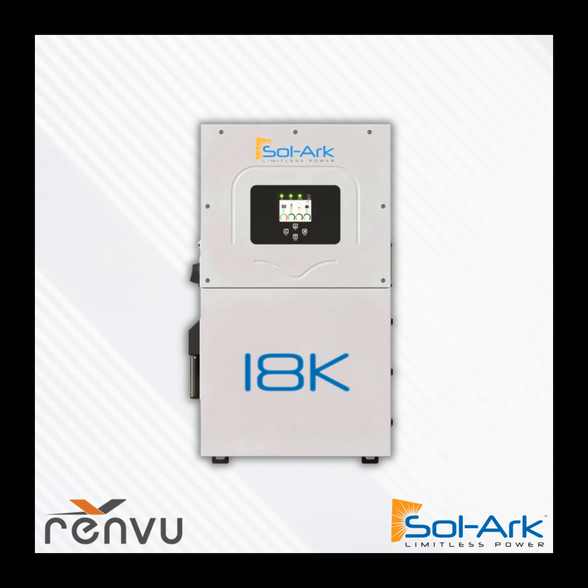If you are not going to power the rapid shutdown system off the manufacturer's AC power supply, and instead run your power off the COM board on the Sol-Ark, just know you can do it with the 18K far more than you could with the 15K. But I would still only recommend doing it with rapid shutdown only electronics, and let the MPPTs of the inverter itself do your shade mitigation.